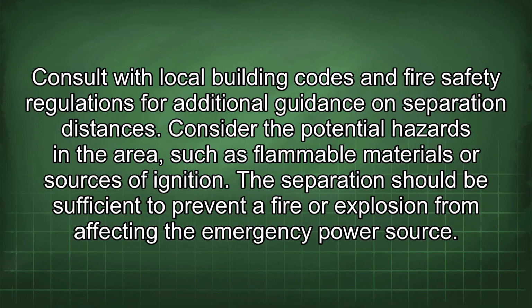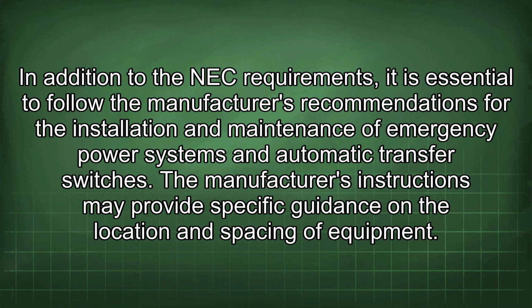Consider the potential hazards in the area, such as flammable materials or sources of ignition. The separation should be sufficient to prevent a fire or explosion from affecting the emergency power source. In addition to the NEC requirements, it is essential to follow the manufacturer's recommendations for the installation and maintenance of emergency power systems and automatic transfer switches. The manufacturer's instructions may provide specific guidance on the location and spacing of equipment.